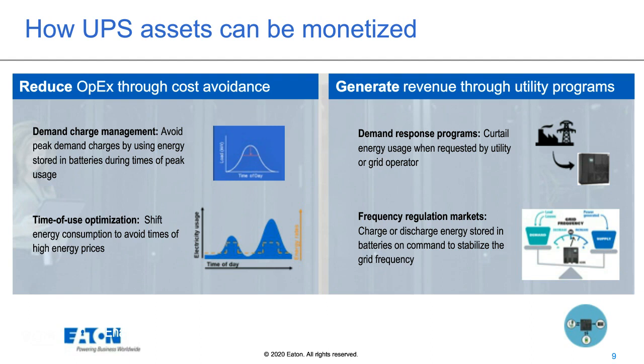By the same token, at 1 o'clock in the morning when the loads are light on the local utility, the frequency tends to creep higher. It's not allowed to do that, so they would normally have to take expensive measures to bring that frequency down. But if all of their distributed energy resources can use that time to recharge their batteries or charge them up to a certain point, then that allows the distributed energy resources to add demand to the grid at the time when the utility company actually needs added demand to keep their frequency under control.